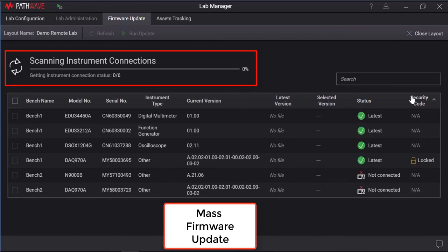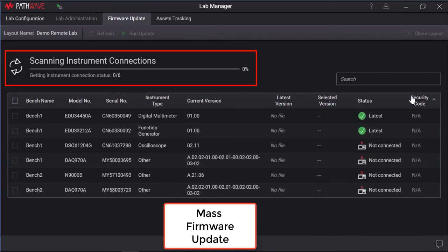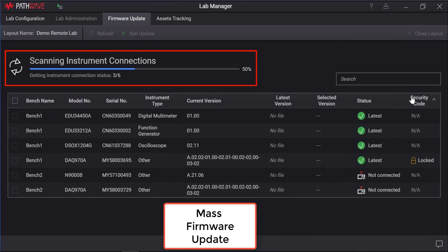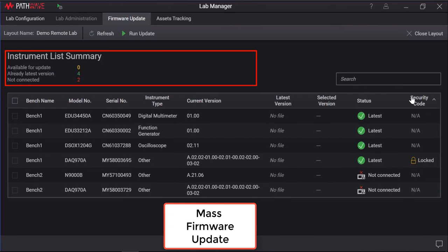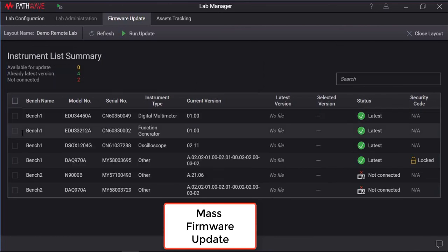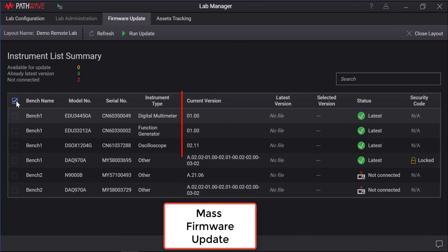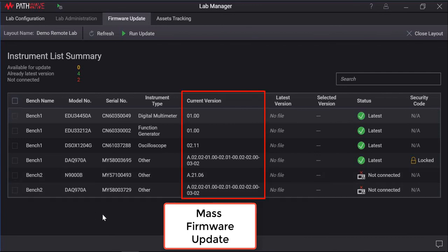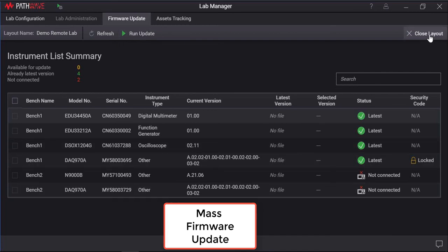The scanning process will take some time. Once the scan is completed, all the instruments in the lab layout selected will show the firmware version of each instruments. Then select the instruments that you wish to update and proceed with the run update. The firmware update will begin and wait for the update process to complete. Thanks for watching!